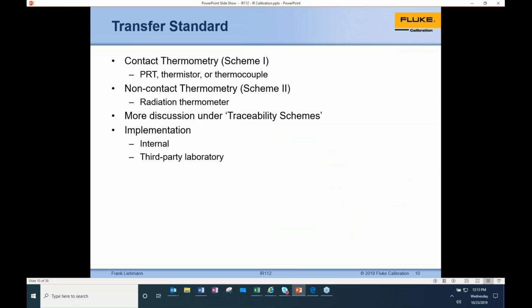So we're going to go through a couple of schemes here that I mentioned as far as contact thermometry versus non-contact. And we're going to show you how we do it internally through our lab. So again, obviously contact thermometry is referencing back to something actually physically touching. Usually it's right behind the black body surface, or in a cavity situation, it's touching right up against the point of the cone internally. In non-contact thermometry, which we're going to call scheme 2, it's all done through radiation only. So everything is being done with the optics of an IR. So again, we'll have a little bit more under this, the traceability schemes that we're going to touch on.